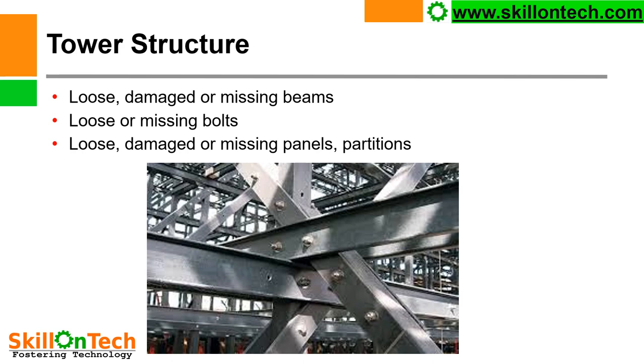Loose, damaged, or missing beams — there may be beams that are loose because their fasteners may loosen during operation of the cooling tower. Any of the beams may also fall due to loosening of fasteners.